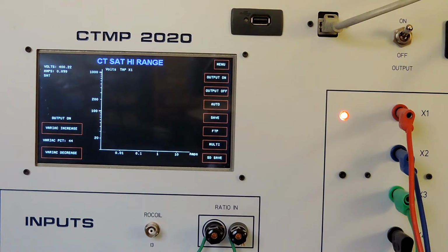Ramping up the voltage, taking voltage and current readings. It says SAT, it is now saturated. Test is complete. Plotted the graph. Now proceeding to the blue X2 tap. I'm going to draw a saturation on that. Slowly ramping up the current voltage to get accurate readings.